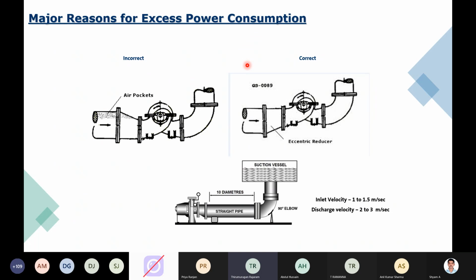Some more points for you to note here: the piping part also influences your pump performance. That impacts your energy efficiency. So here you can find this piping is a kind of concentric design with the bottom flat. So that helps create an air pocket because of the water level difference.